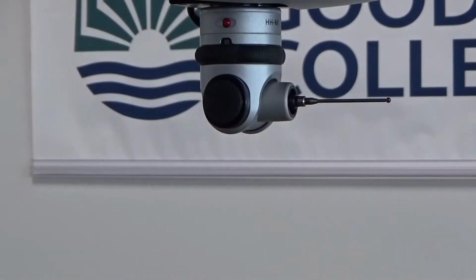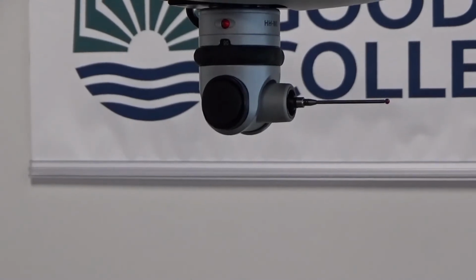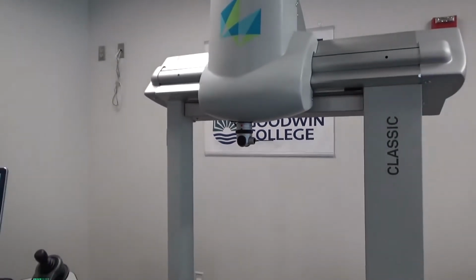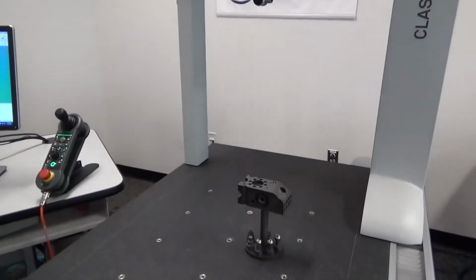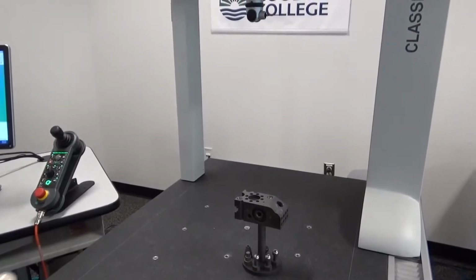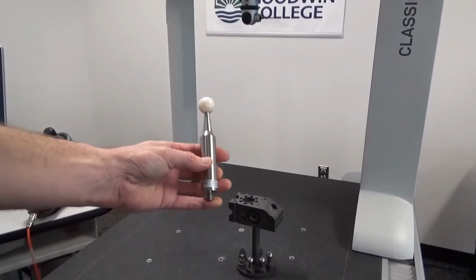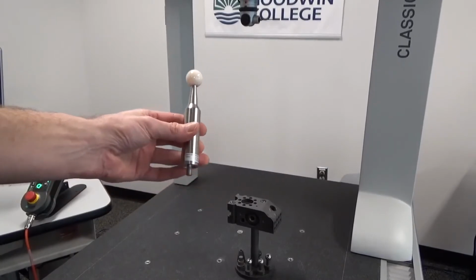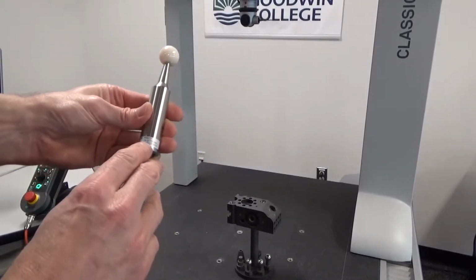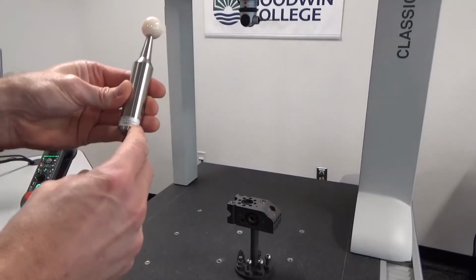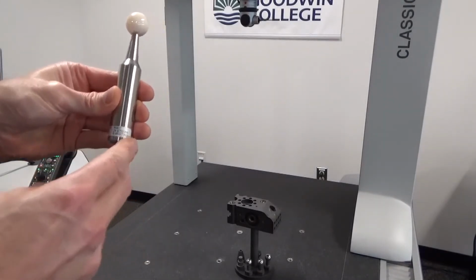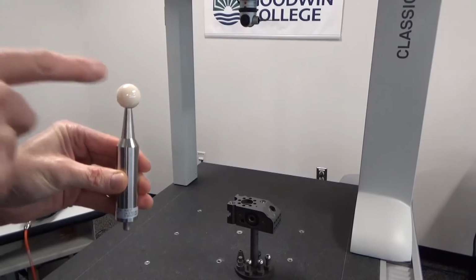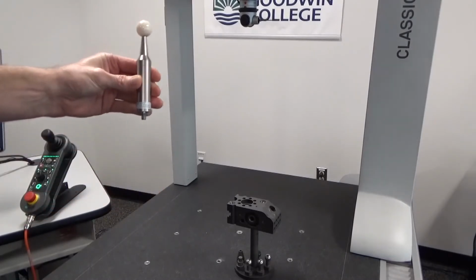So for every one of those positions that we have, we need to put a calibration in place for this probe. So the way this is done is we mount a special calibration sphere down onto the table. This is the calibration sphere. It comes with the instrument, and on it, it has information about how big the sphere is written right on its face. And that's information that needs to go into the software so that it knows just how big the sphere is when it's making measurements around it.